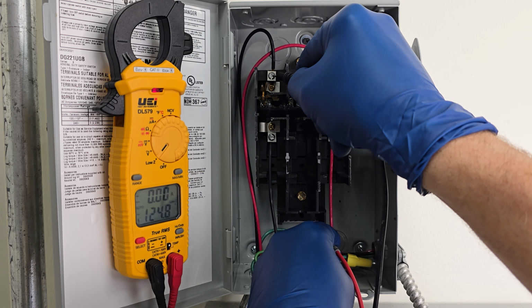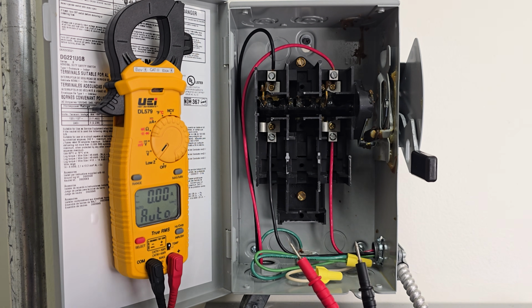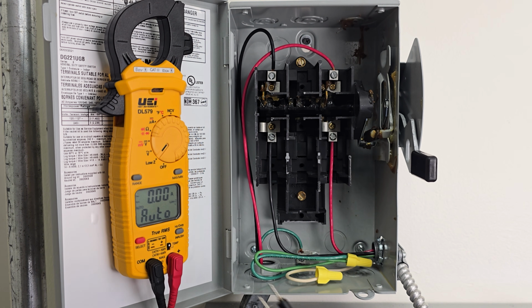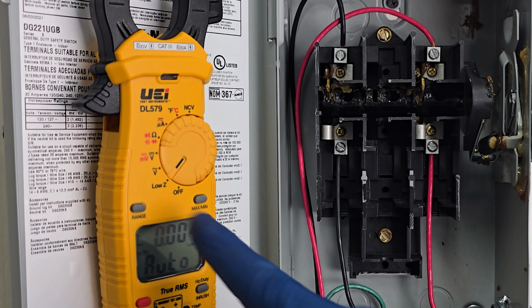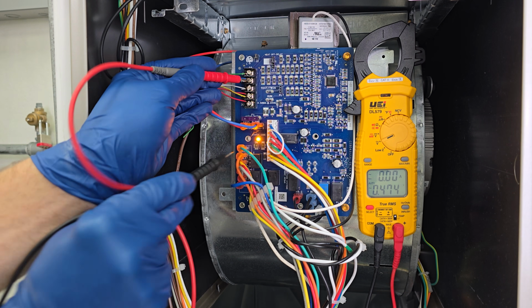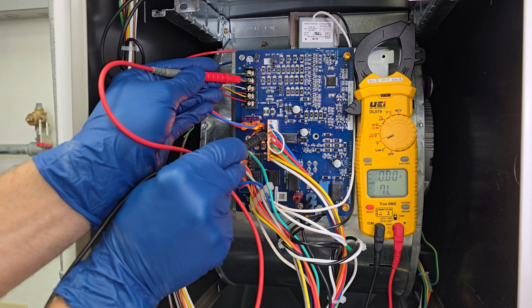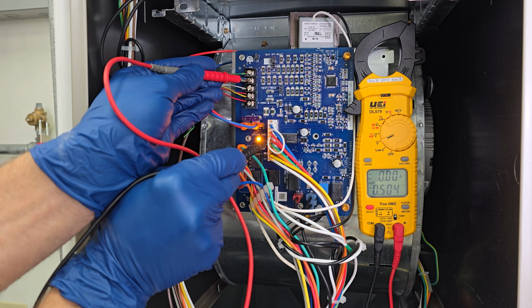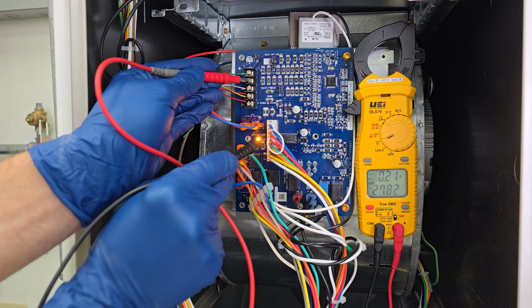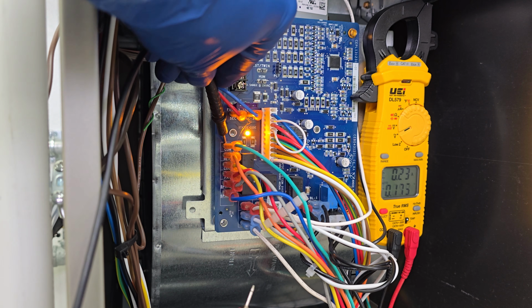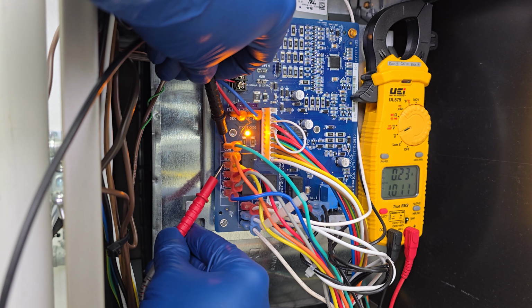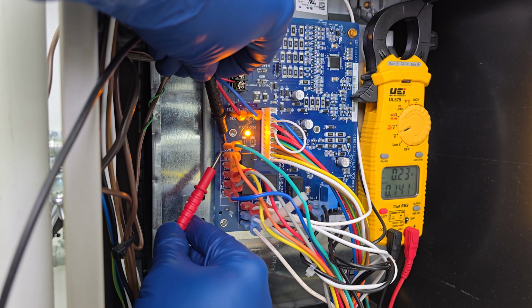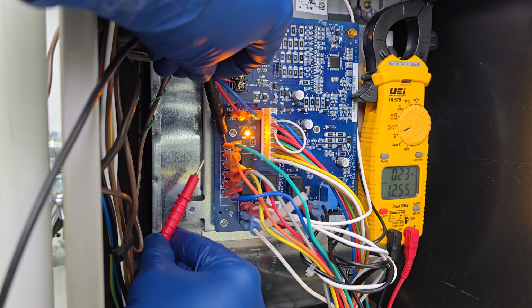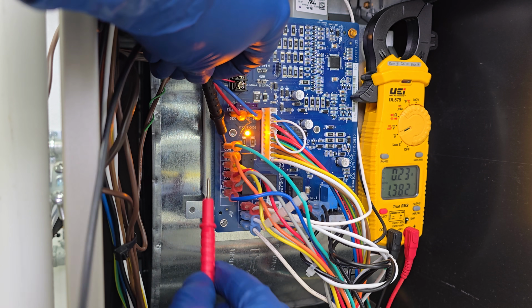So we can get the actual real voltage that is present here by switching over to the low Z in a scenario like this. Now, in an HVAC unit, we typically don't use the low Z function because the multimeter adds extra current onto that circuit being measured, and so we don't want to accidentally damage any of the sensitive electronic components on the circuit boards inside that unit. So we just use the low Z function for high voltage testing.